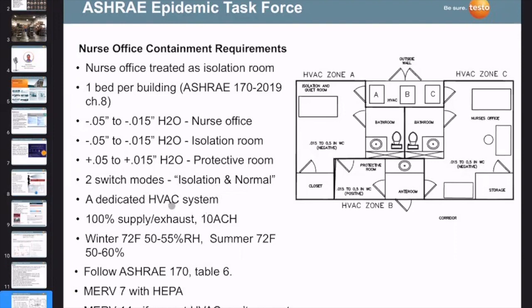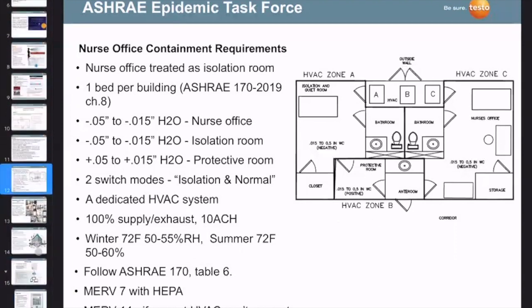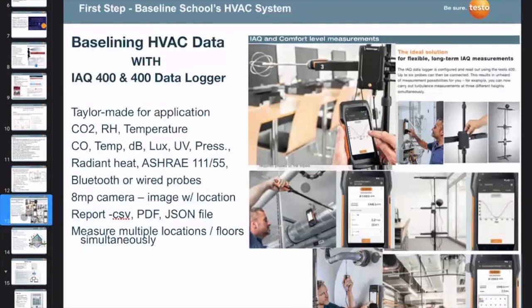And this will be a dedicated system separate from the school system. Okay. And ASHRAE 170 Table 6 is really that same specification, which talks about the filtration level needed for an isolation space like this. So case in point, we're actually changing the operating parameters of some school areas to really kind of mimic that of a hospital isolation application.